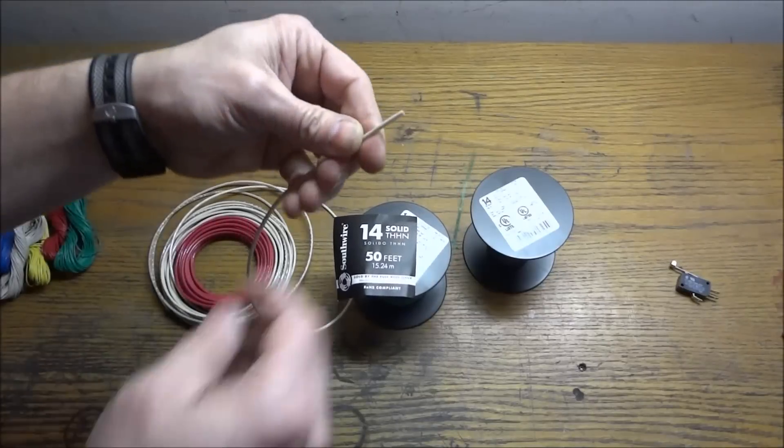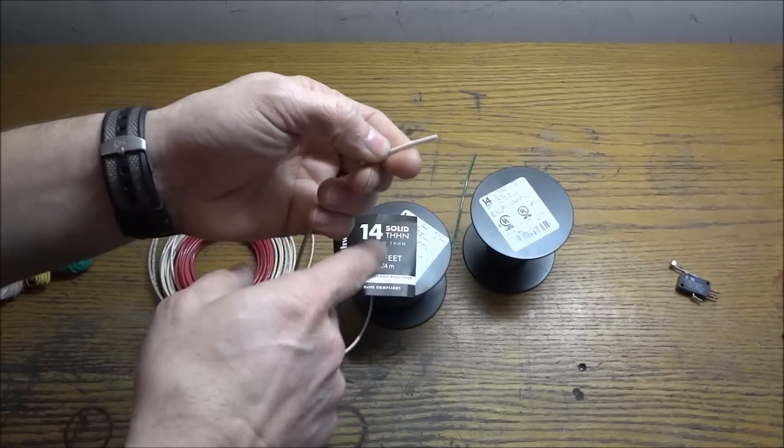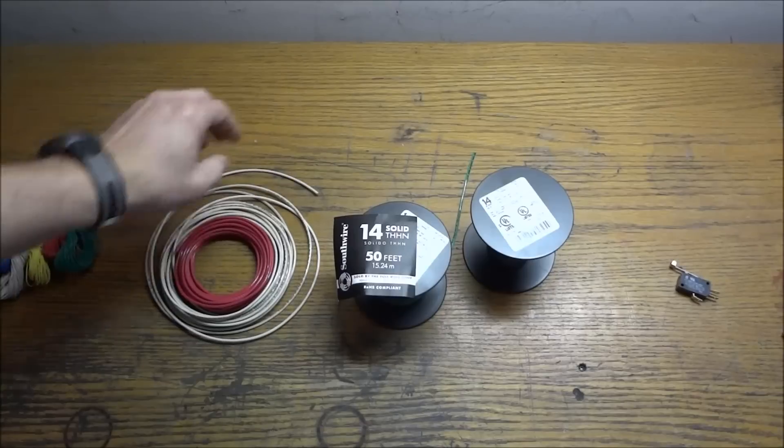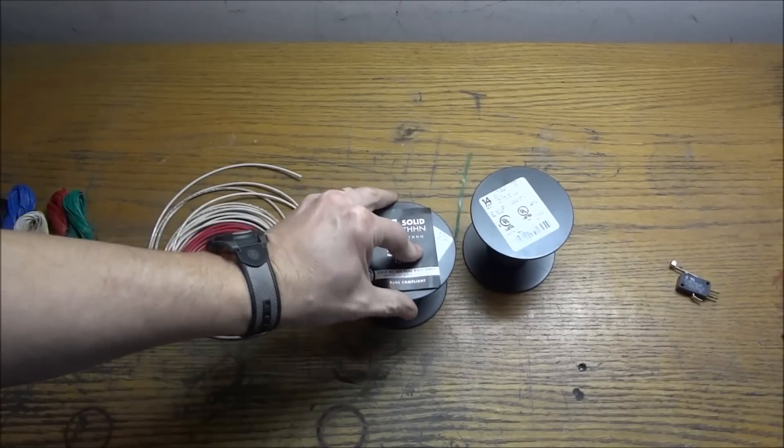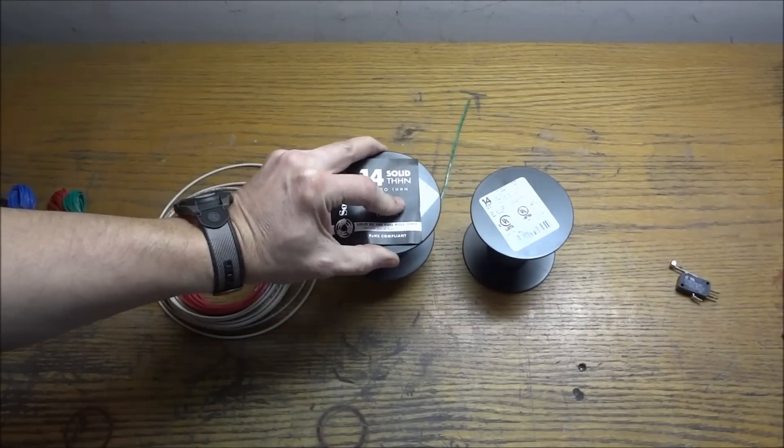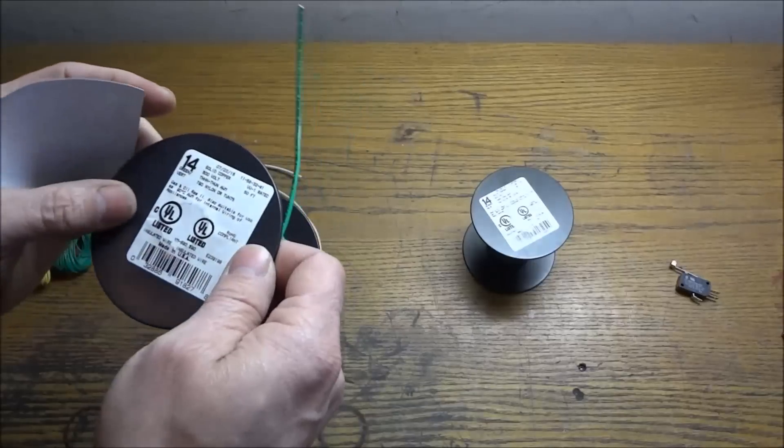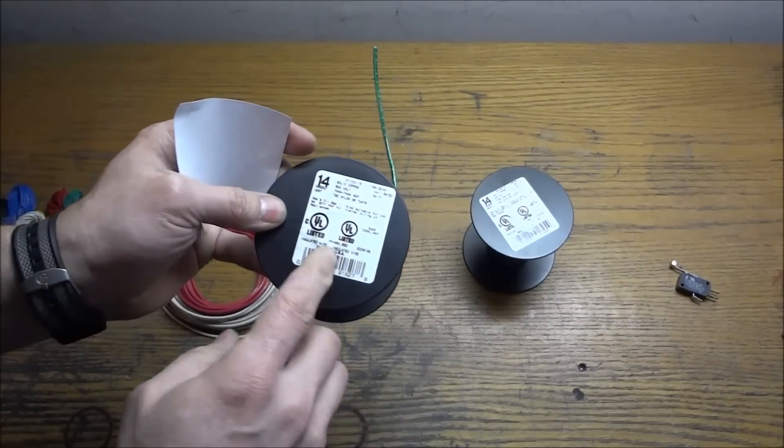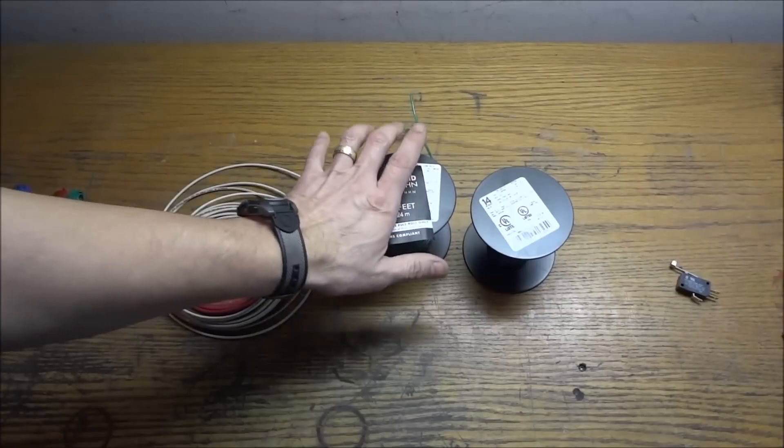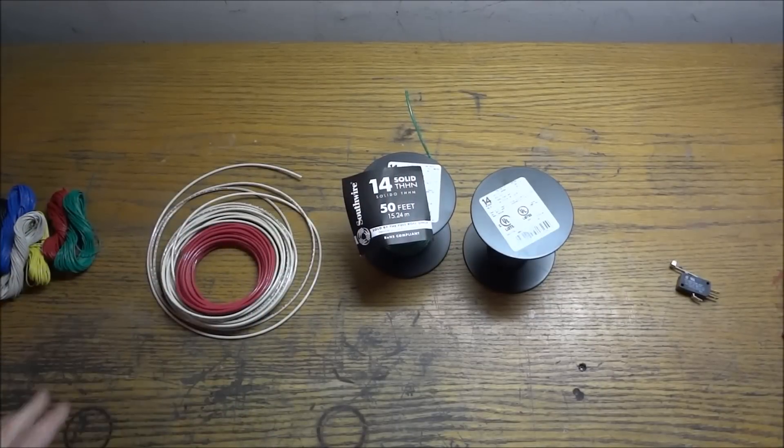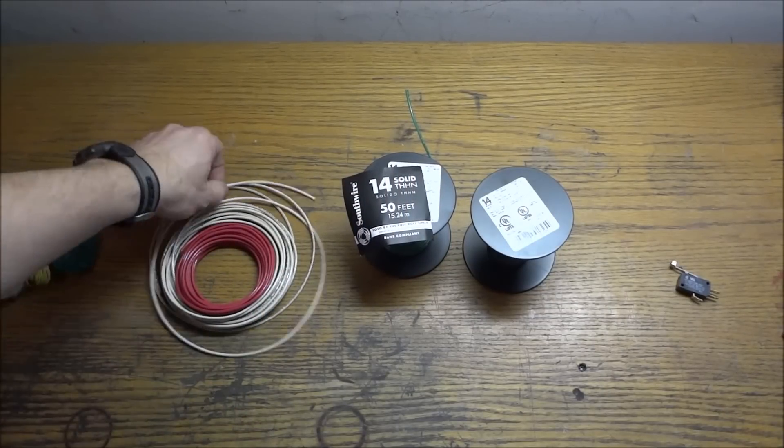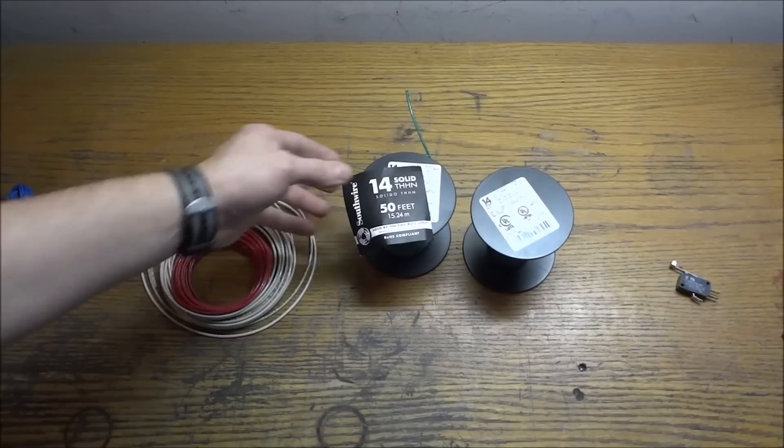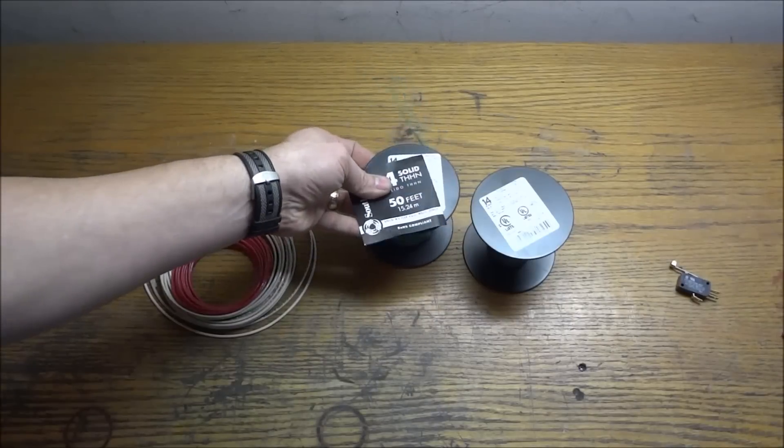I like using the solid core because you don't have to worry about stray wires. If you do use the stranded then just tin the end of it. That's what I do and it keeps everything nice and tight and tidy together. You can use 16 gauge inside the panel. But I have some 14 gauge here that I'm going to run to my outlets. But for your control circuit we're not going to be pulling a lot of amps so you can use 16.